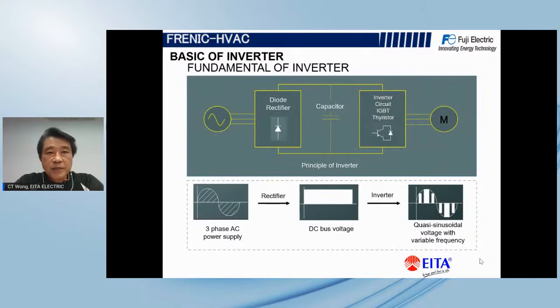Let's quickly explain a little bit of the basics of inverters. Inverter technology, as I say, is three-phase coming in through diode rectifiers, smoothened by capacitors, and then switched back by the IGBT to the motor. This IGBT will switch back a sine wave to the motor in order to get the AC motor running in the VVVF format. So this is the basics of the inverter, and this is where the inverter name comes from. They invert from AC to DC and DC to AC again.